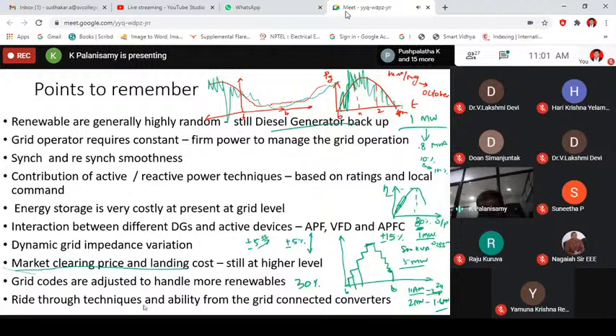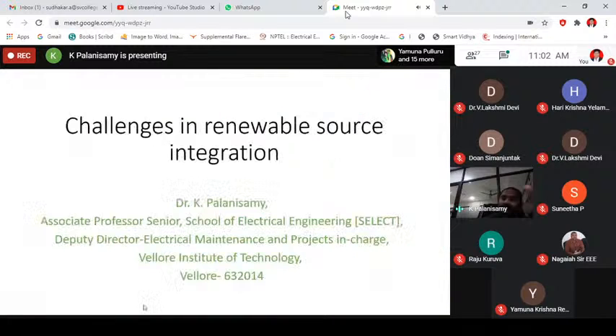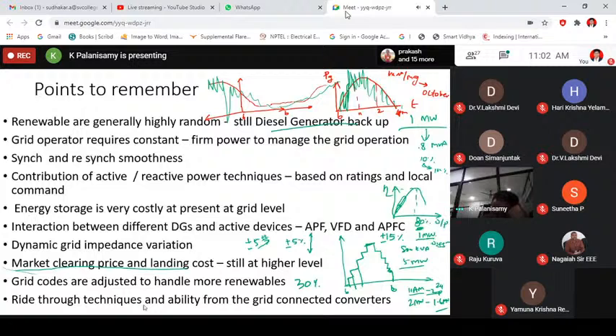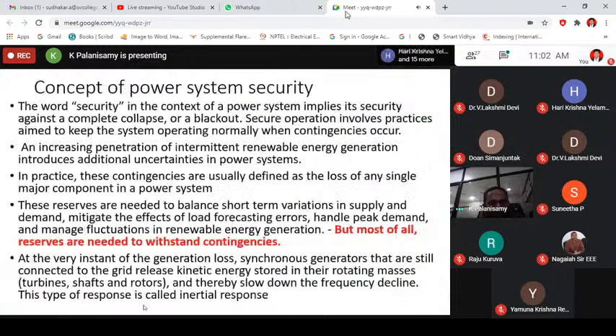Since you are contributing the fault current locally, the entire fault current need not come from faraway places, so the recovery, the restoring time, is somewhat quicker. In all these ways you can support the grid, so that you can help the grid function smoothly. Okay, so all these are important points when you connect renewable sources to the grid. You can say the challenges lead to research opportunities. When you have more and more challenges, you get openings to do research, so that you can contribute to the electrical engineering field. Of course, all these other things are actually conventional slides.